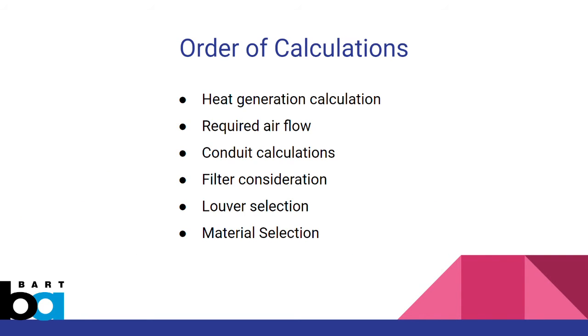The steps we took to get this far within the project are the following. The heat generation calculation to figure out how much heat to remove, the required airflow to figure out how much air to put into the train car, conduit calculations to figure out the sizing and the pressure drop, filter consideration to make sure the passengers are safe, louver selection, and lastly, the material selection for the protective casing.